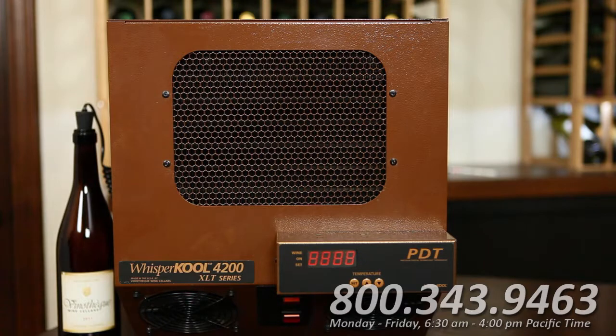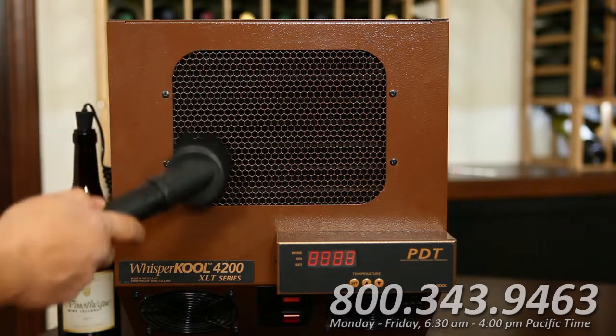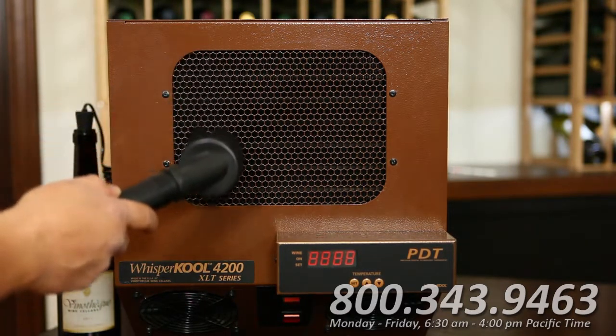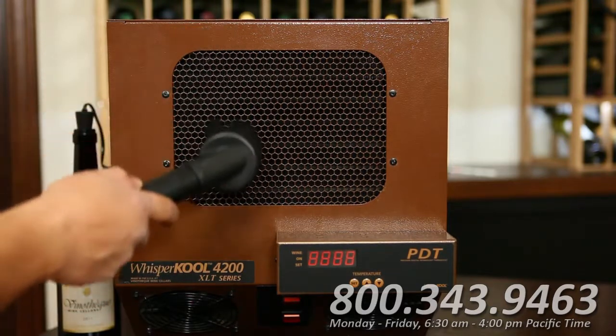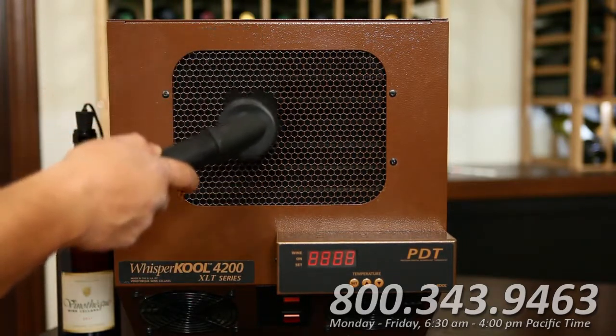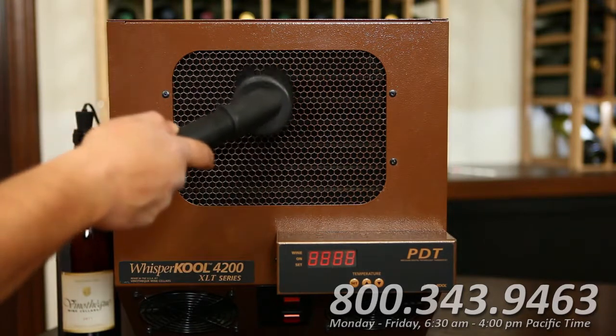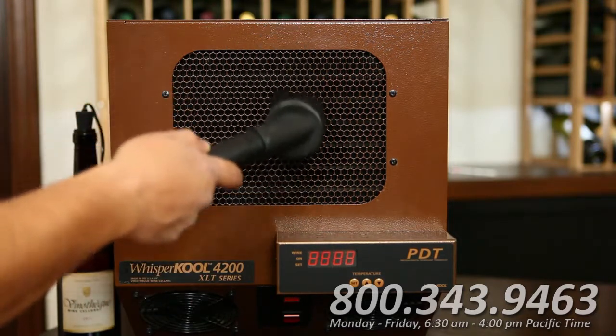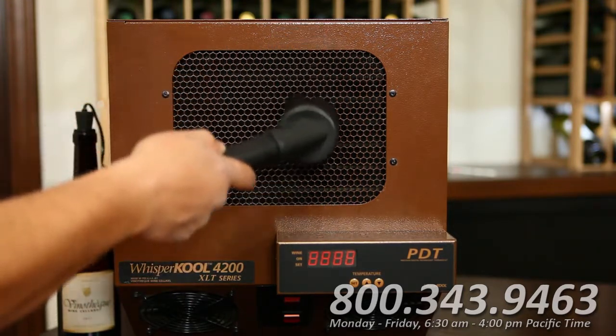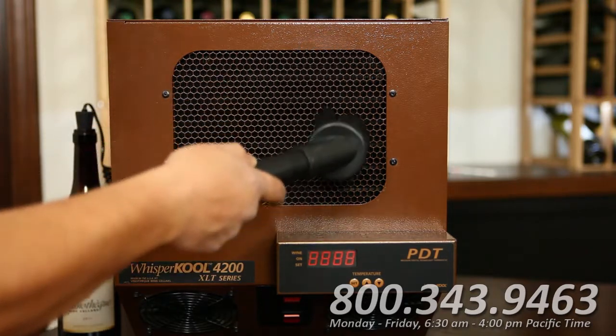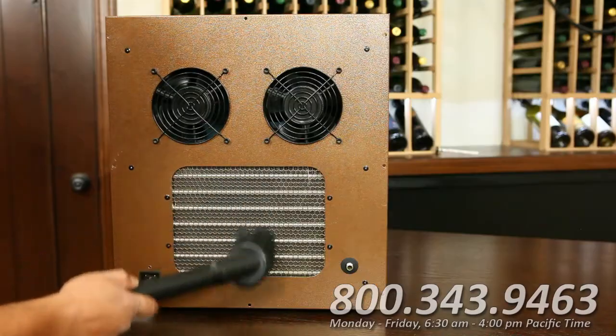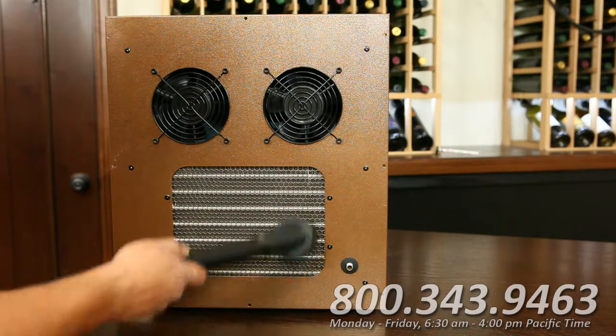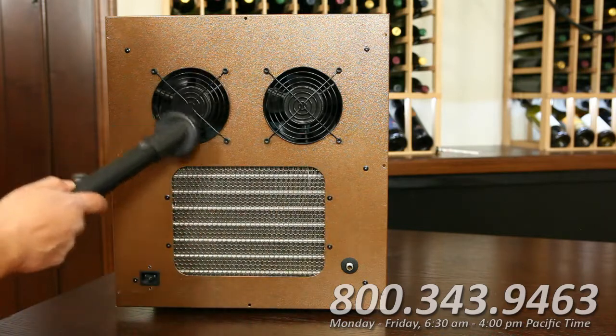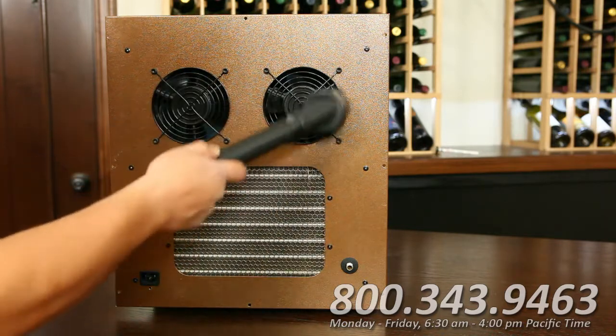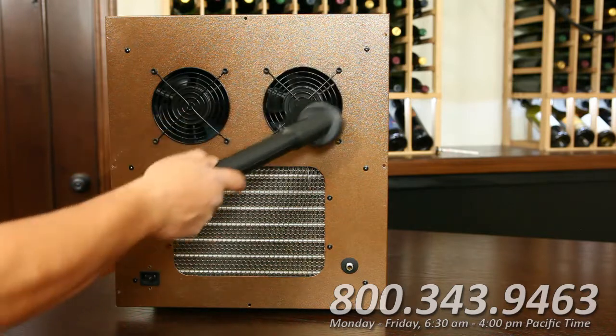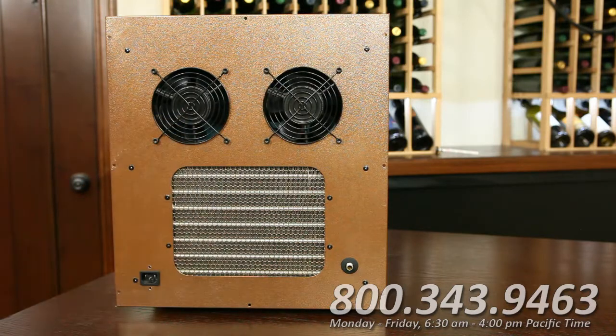Our first troubleshooting step will be to clean the coils and perform any general maintenance that is prescribed for your cooling unit. To clean the coils, use a vacuum with a brush attachment. Vacuum the surface of the grill in an up and down motion and remove any dust or lint that has accumulated. Clean the grills on both the condenser side and the evaporator side and vacuum the fans also. We do this because dirt on the coils acts as an airflow obstruction, which makes your unit work harder to achieve proper performance. Remember to perform these steps every 3 months as regular maintenance.